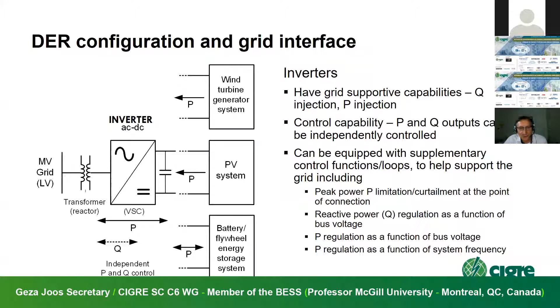So what the battery energy storage system has, because of the presence of the inverter, is complete active and reactive power control. You can provide reactive power and real power independently, and you can put into the inverter all the intelligent functions that you would need.